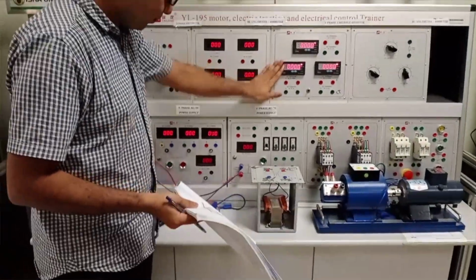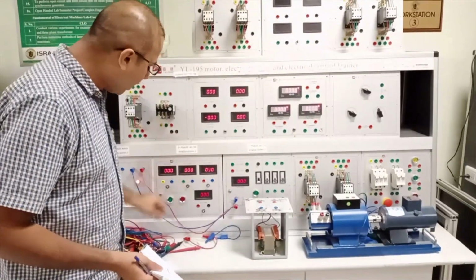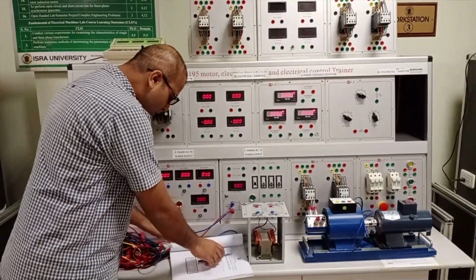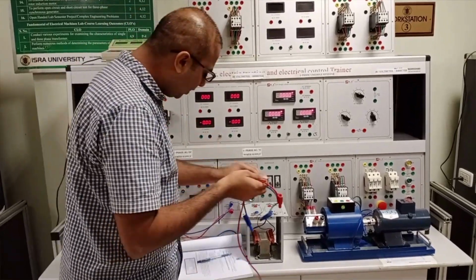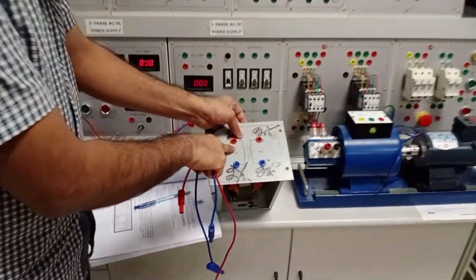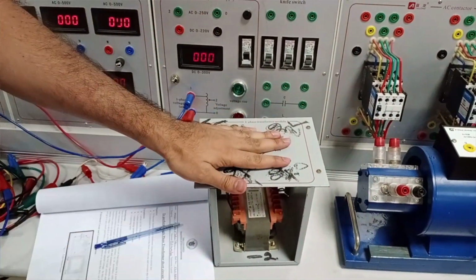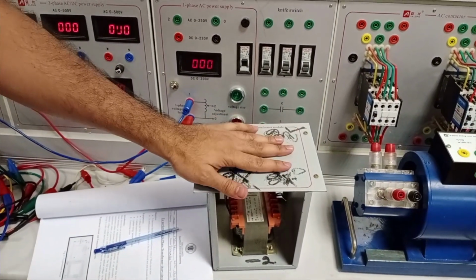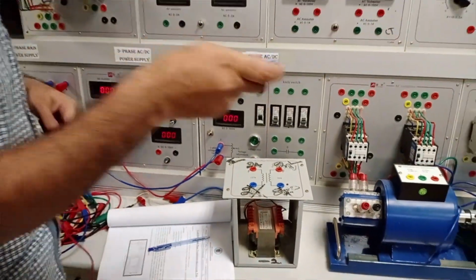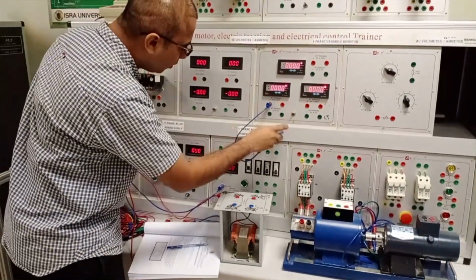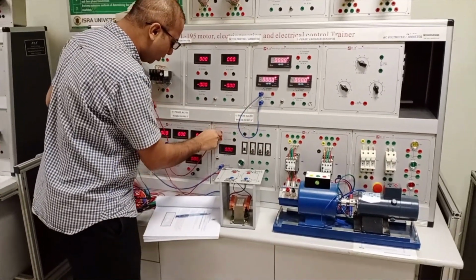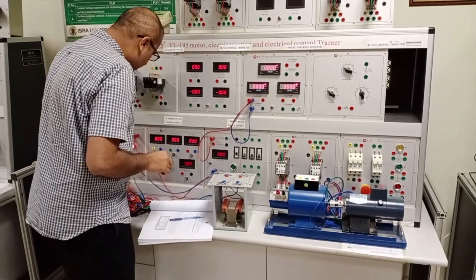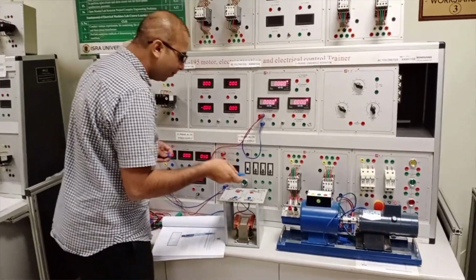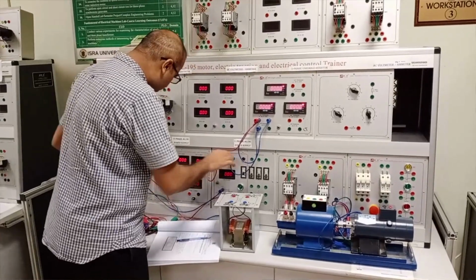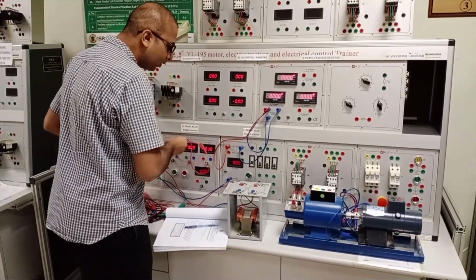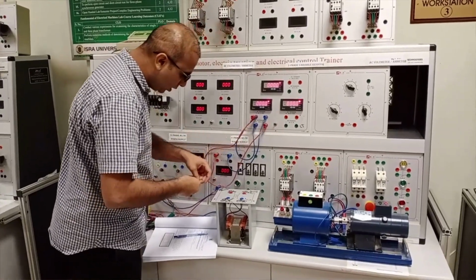Again we need the wattmeter, the transformer, the AC supply and the connecting wires. So what we have to do is connect this high voltage winding to this wattmeter and the supply, and keep this low voltage winding short circuited. Again, there are the two coils of the wattmeter, the current coil and the pressure coil. The two points will be short circuited and this point will be connected to the neutral one. And this point is connected to the high voltage.